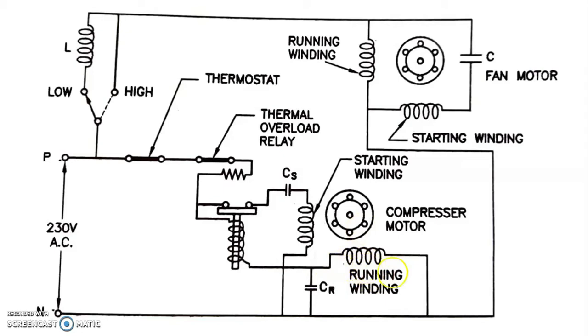We have two windings: a running winding and an auxiliary or starting winding. We have two capacitors — one is a running capacitor and one is a starting capacitor. The running capacitor permanently remains in the circuit, while the starting capacitor and starting winding are disconnected from the circuit once the motor picks up to maximum speed.